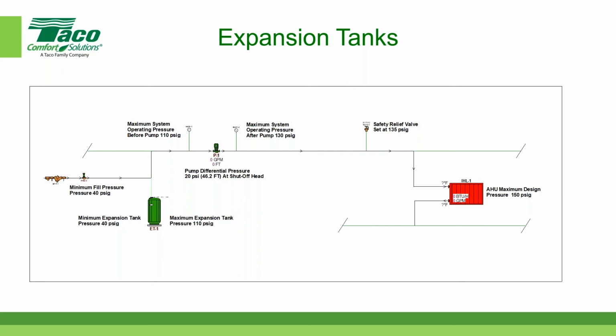So in our example, the fill pressure has to be 40 psig, and that's done at the pressure reducing valve. Usually these PRVs are adjustable, and in this case, we would set the PRV. I haven't shown every single thing on this, but you could put a pressure gauge here, and when that pressure gauge reads 40 pounds, you adjust the pressure regulating valve until it reaches, in our case, 40 pounds. And then at that point, if the pressure drops below 40 pounds, it'll add water. If the pressure goes above 40 pounds, the valve will shut off.